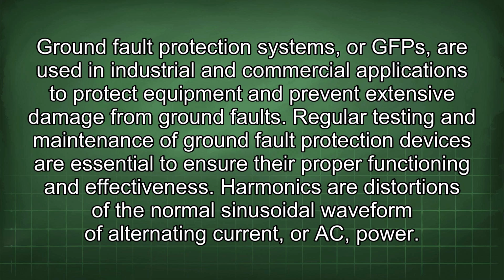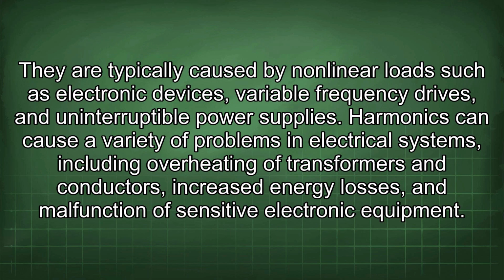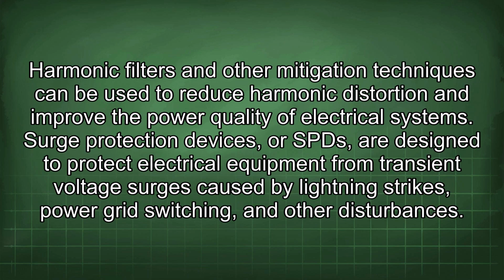Harmonics are distortions of the normal sinusoidal waveform of alternating current, or AC, power. They are typically caused by nonlinear loads such as electronic devices, variable frequency drives, and uninterruptible power supplies. Harmonics can cause a variety of problems in electrical systems, including overheating of transformers and conductors, increased energy losses, and malfunction of sensitive electronic equipment.